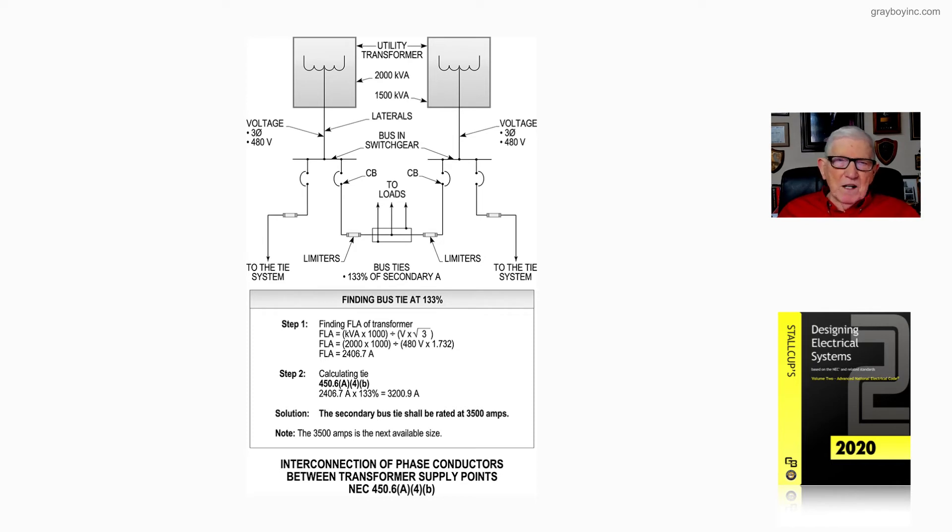Now the application of 450.6(A)(4)(b), we take the 2,406.7 amps times 133%, and we come up with a value of 3,200.9 amps.